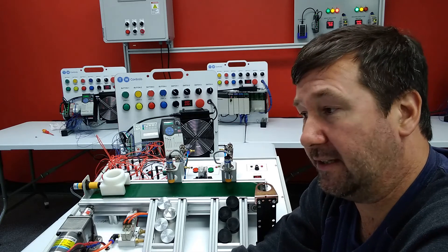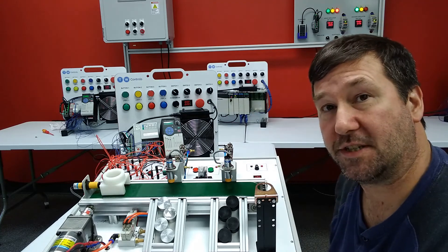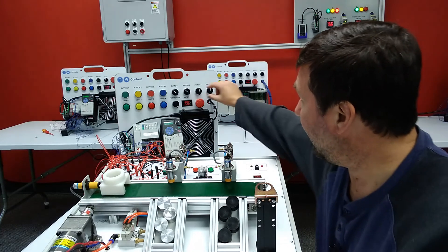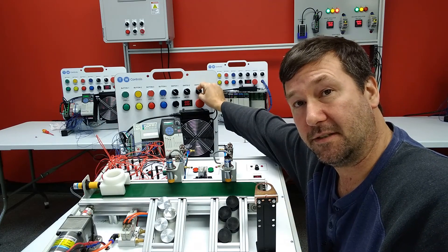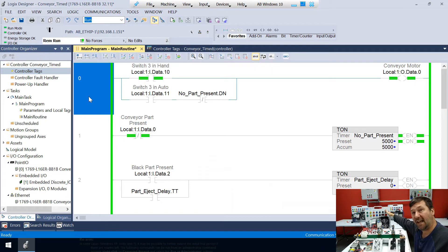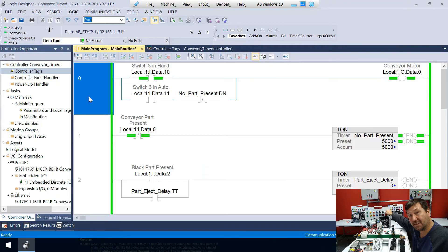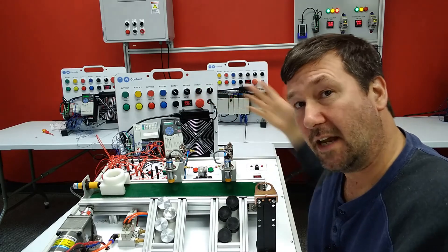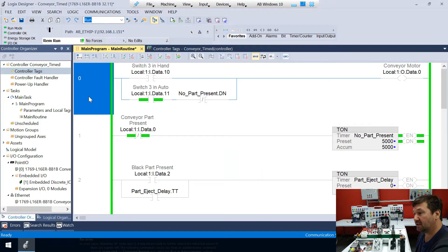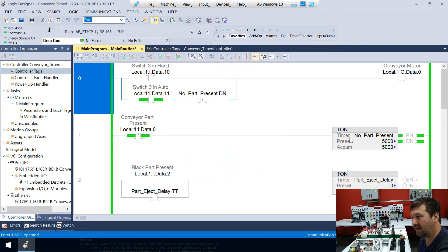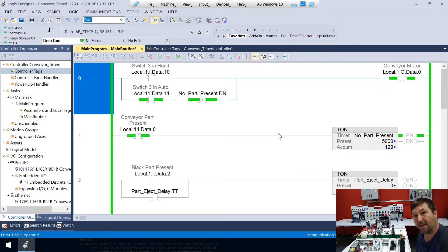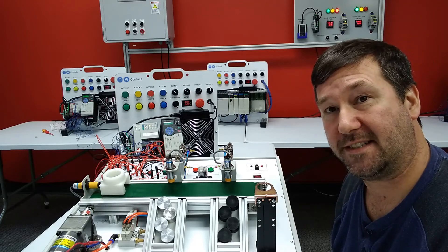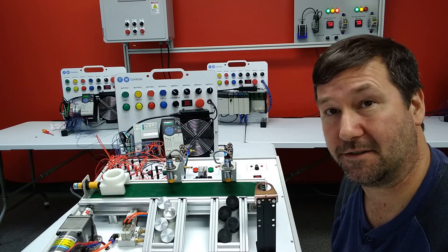Switch three is in the middle position and nothing's happening. So now let's switch switch three to the left position and our conveyor is going to come on and it is in hand. Now we switch it to the middle position and it immediately goes off. Now let's switch it to the right position. Now it doesn't actually come on because right now our part present timer is done. We can see that right here. And now let's drop a part onto our conveyor and immediately our conveyor starts back up. Part gets ejected and when we're done the conveyor turns off.